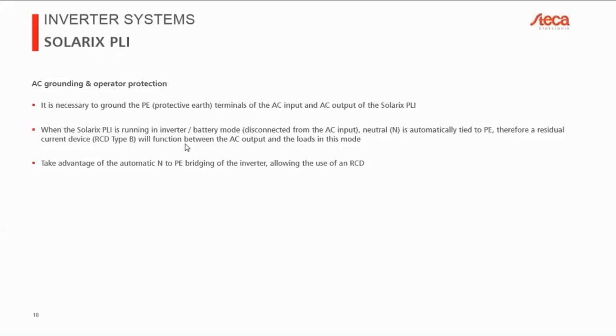In other words, the connection between ground and neutral is no longer there. For this reason, as soon as the inverter switches over to off-grid mode, we automatically, with the same relay that is used to switch over, connect the neutral and ground lines together. This is to ensure that if you're using a residual current device, an RCD, to protect people from high voltage on the AC output side, as you would in most homes, you don't need to worry about the bridging of the neutral and the ground, because this is typically already existent in your home. And for the off-grid mode, the inverter is basically taking that over for you.